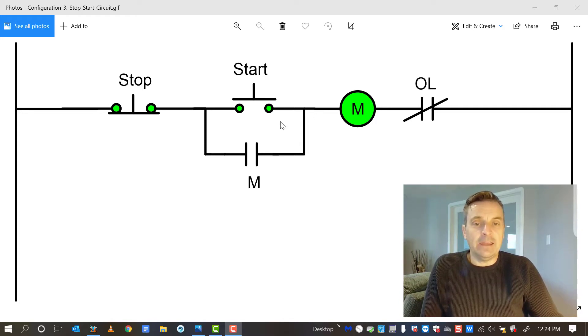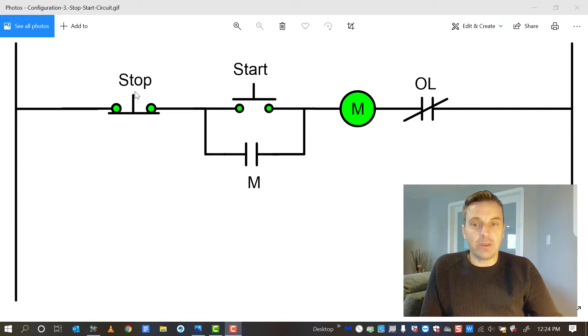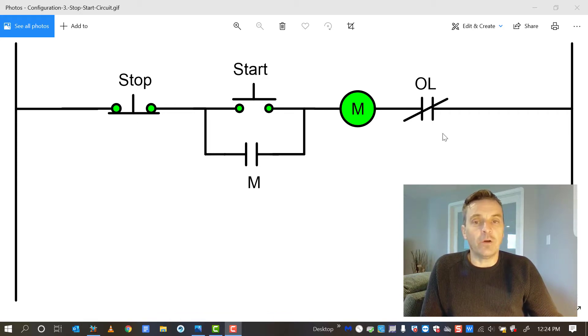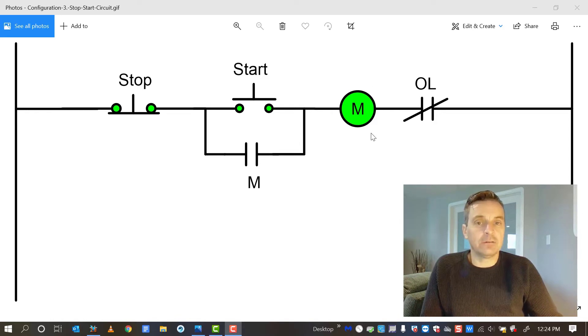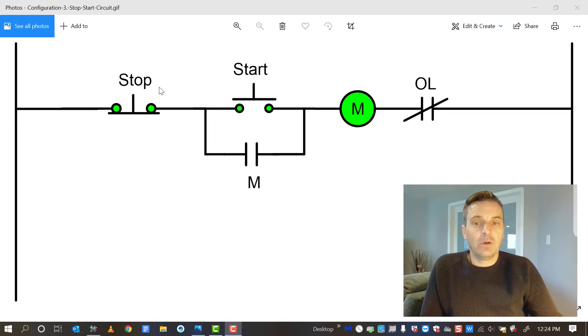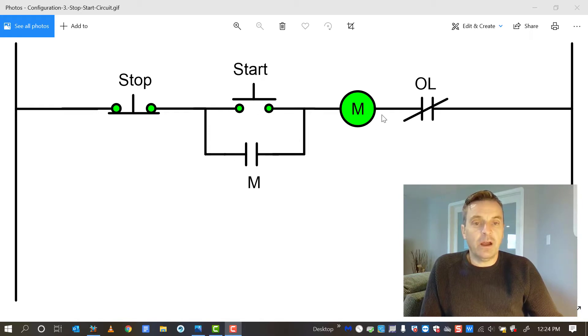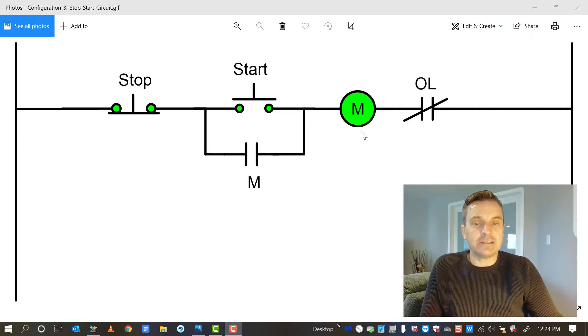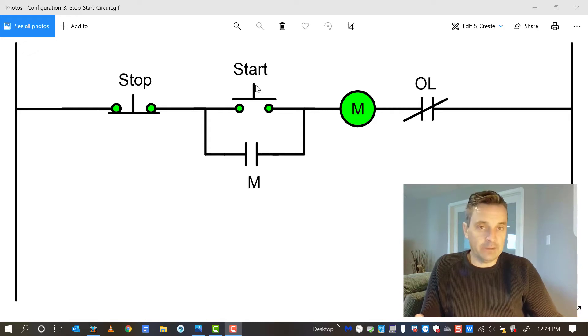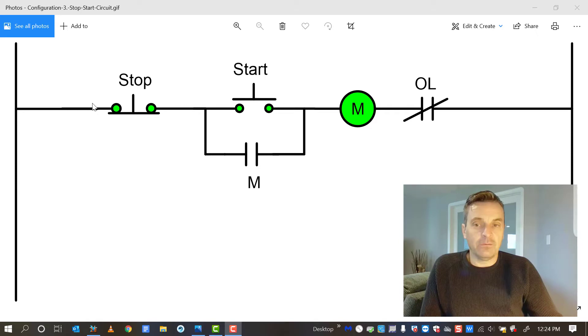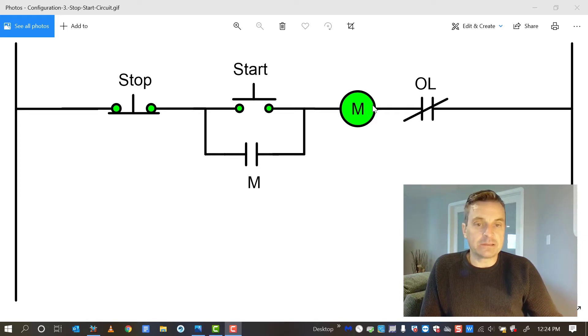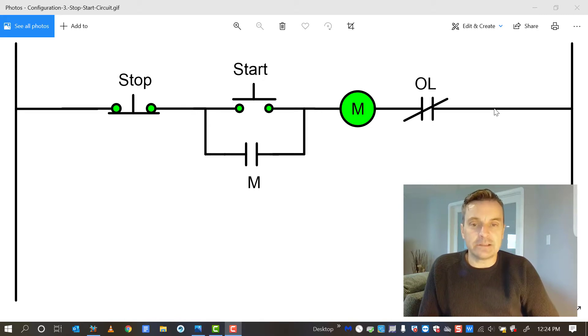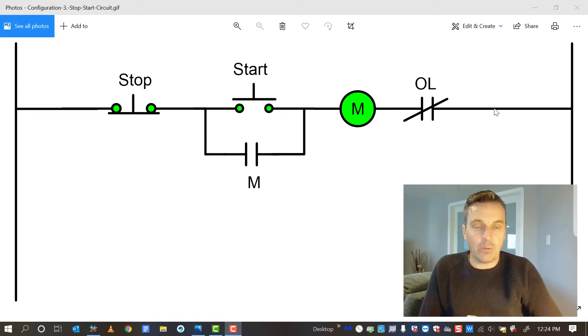Anything that would break that circuit, whether the stop button is opened or the overload contact is opened, would effectively shut this down. This is like an or statement here, so when I press this start button, this motor coil energizes, and there's an auxiliary set of contacts that would close. Then I'm able to take my finger off the start button because these are momentary, and I would have current flowing down through this path keeping this coil energized. That's essentially how that works.